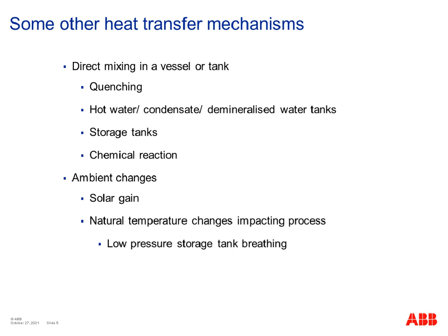Heat transfer doesn't just occur where we have two separate fluid streams. It also occurs where there is direct contact between the fluids. It could also be due to ambient changes in the environment impacting the process. So for example, you could have direct mixing in a vessel or tank due to quenching, mixing of streams such as in demineralized water tanks, mixing of material in storage tanks, chemical reactions which may give way to heat being produced by the reaction, energy changes in the process. And as before, we have ambient changes such as solar gain from the environment and natural temperature changes impacting the process. A key example of that would be the breathing in and out of a low pressure storage tank to account for those ambient changes. So we'll need to consider pressure relief in these scenarios.